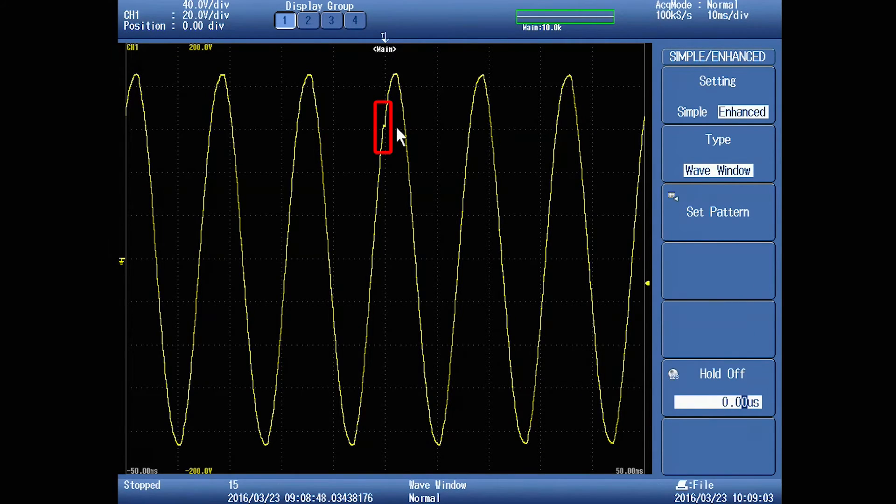That very small glitch is difficult to trigger on. It is not a simple level trigger because typically the sine wave output of the UPS can be simultaneously higher and lower level than the glitch's absolute voltage level.